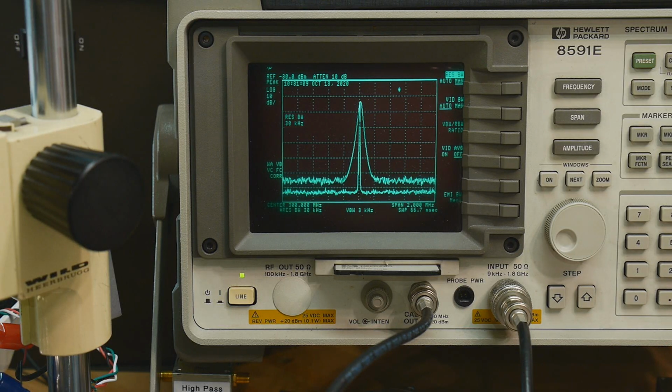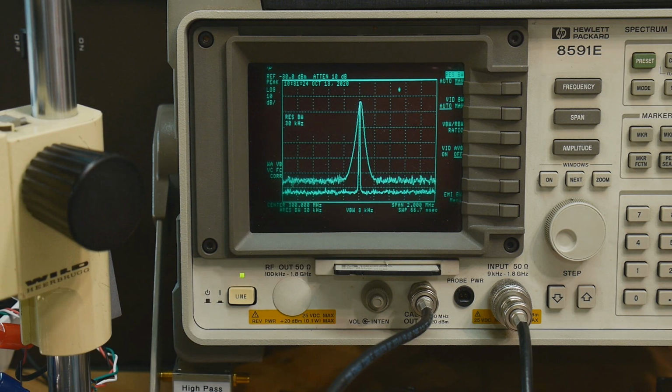Okay, I wanted to show you a concept. It really helped me. I saw it in a video once produced by Agilent, and the way the graphics were done gave me a lot of information. So what I'm doing here is showing the cal output. This is 300 megahertz, and I'm going to show it at different resolution bandwidths.